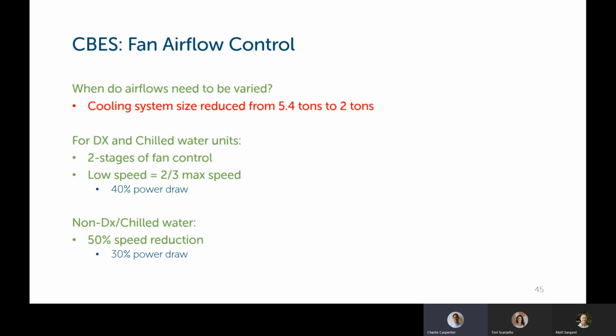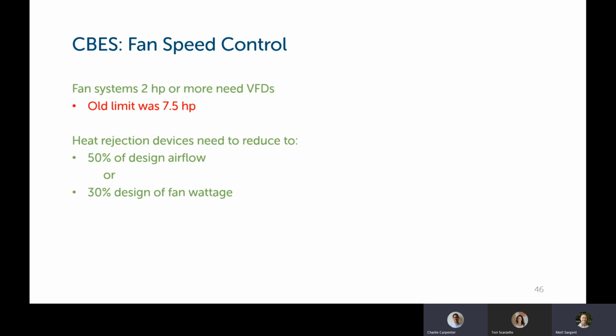For direct expansion and chilled water units, you need to have at least 2 stages of fan speed control. The low speed needs to be at least 2/3 the maximum speed or 40% power draw of maximum speed. And for any non-direct expansion or chilled water units, it must be at least a 50% speed reduction in the fans or at least 30% power draw from maximum design. Next slide.